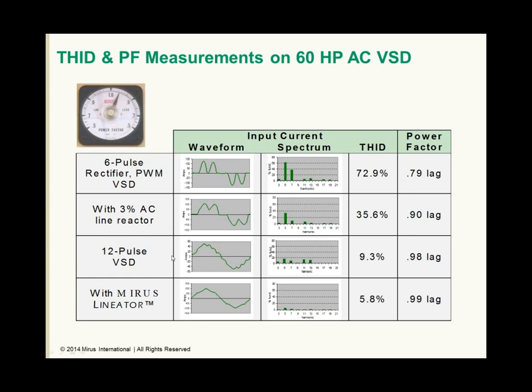Many drive manufacturers will offer phase shifting multi-pulse drive systems. 12 pulse and 18 pulse are very common. The 12 pulse system is shown here. We can see the current now, due to the phase shifting and canceling of harmonics that it introduces, is again more sinusoidal. There are certainly residual harmonics in the power system. In this case, we're at 9.3%. This is a very good functioning 12 pulse drive, and power factor is improved to 0.98.